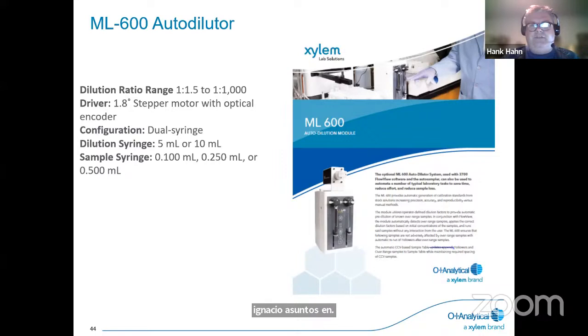So we did launch last year our ML600 diluter. We partnered with Hamilton, as they're one of the best in the industry in providing dilution capability and instruments. So we have a dilution range of 1 to 1.5 to 1 to 1,000. We use stepper motors with an optical encoder. It is a dual syringe. Your dilution syringe can be 5 or 10 mL, and the sample syringe is 0.100 mL, 0.250 mL, or 0.500 mL.